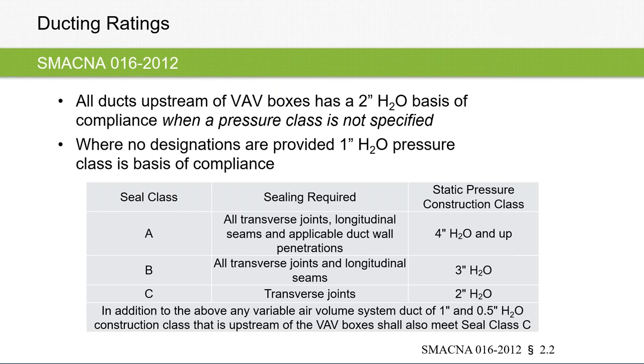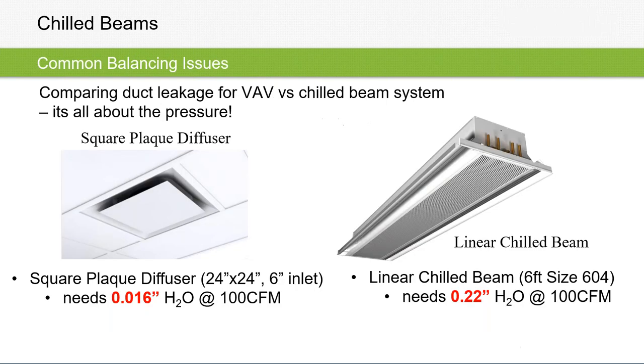Even though it's within SMACNA or recommended standard leakage levels, it can still cause some problems. You will have some leakage, but keep that in mind when you size your air handlers and your ducts. Just know that it's going to be there, and maybe oversize just a little bit to make up for that.